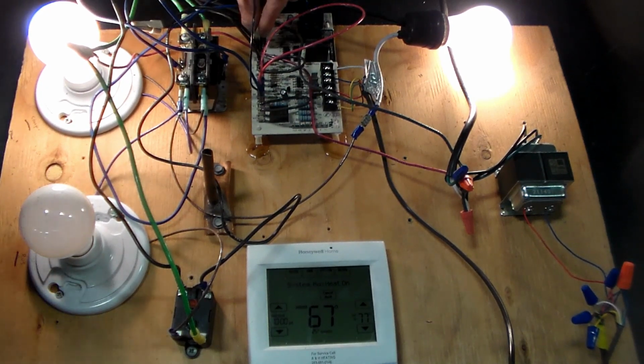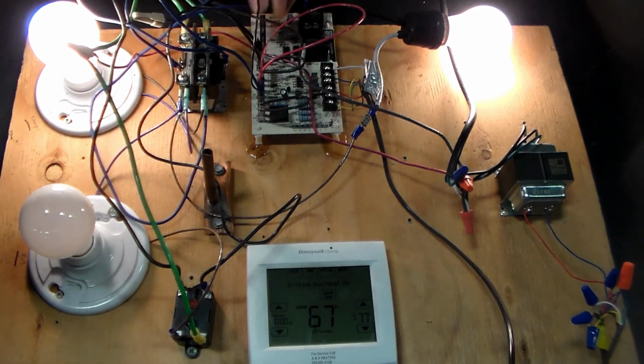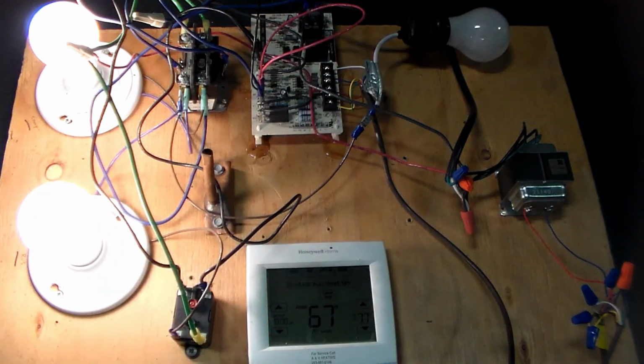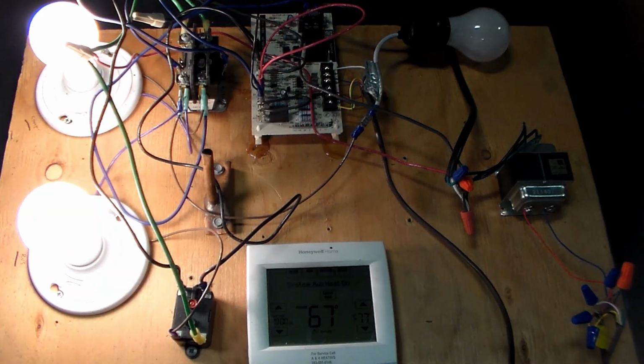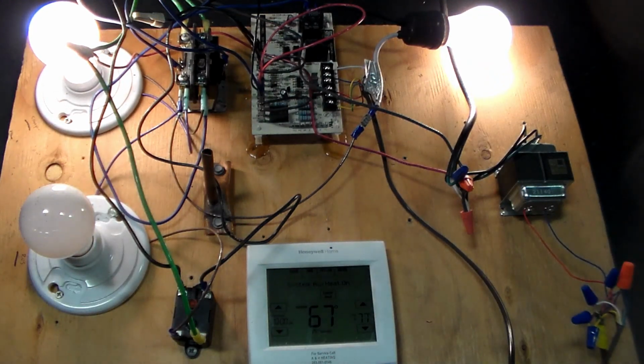Now when we jump that out, it should be able to go into test mode again. There we go. Reversing valve comes on, condenser fan goes off. And of course that's going to kick back out because of the way I have it set up. But if the coil's frozen, then it's going to stay in defrost, not through test mode, but through normal defrost mode until it's thawed out.